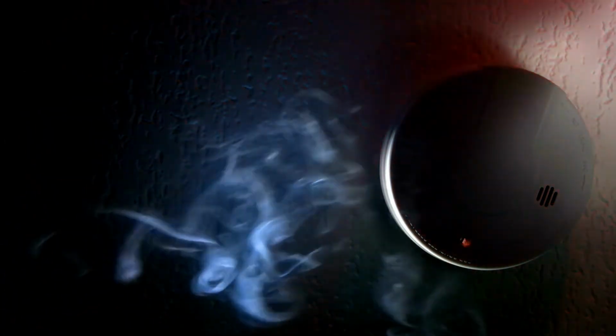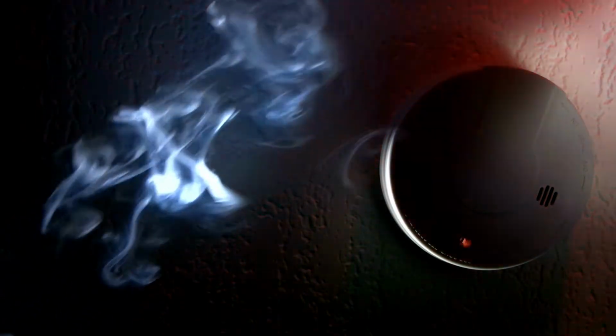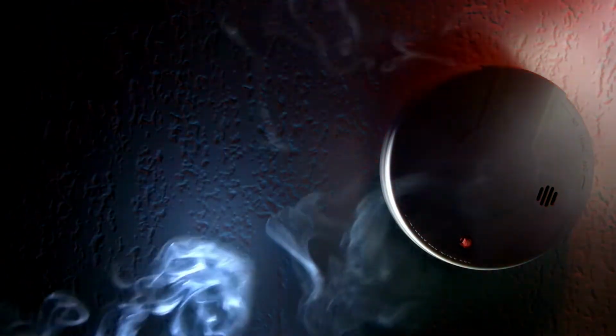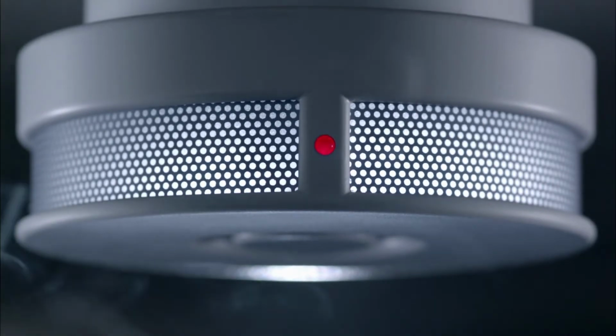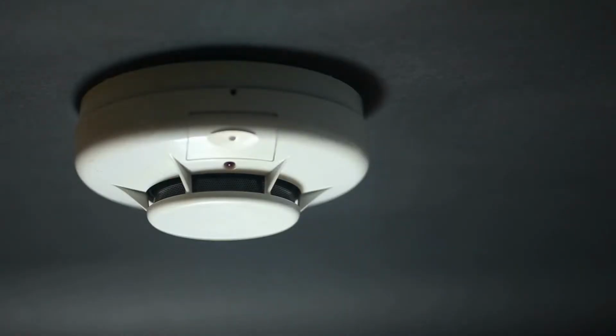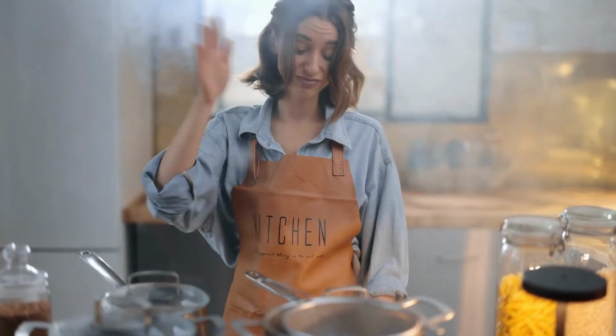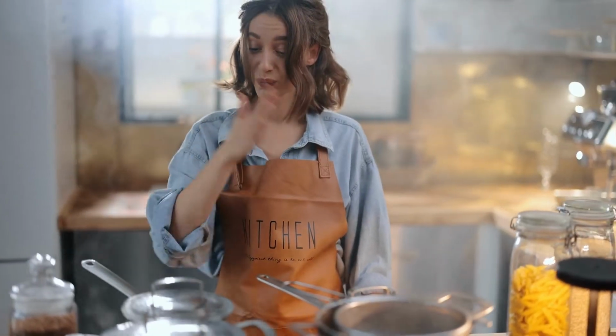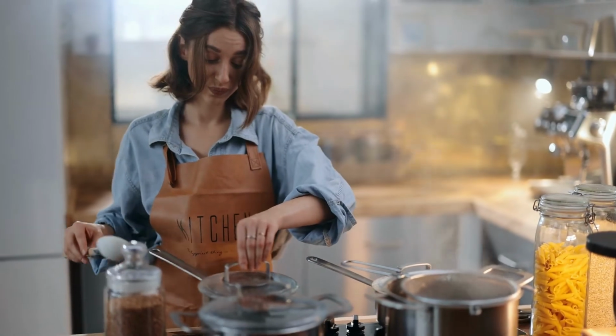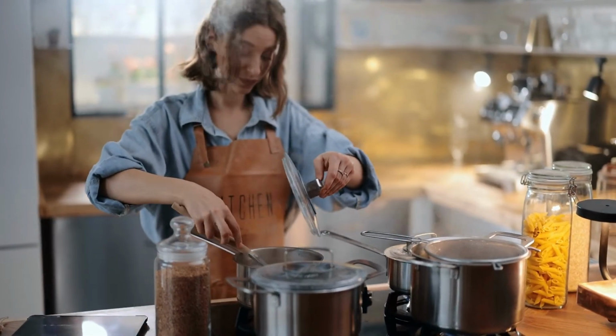Smoke detectors. Smouldering or slow-burning fires can sometimes generate little heat, making it difficult to detect via heat detectors. Smoke detectors are activated when they detect smoke and may release an audible alert earlier in the development of a fire. In some cases, smoke detectors are recommended over heat detectors, since they can detect a fire before heat detectors can. However, if the alarm's coverage space accumulates dust, this can elicit false alarms. Therefore, heat detectors might be a better fit for some people. Smoke detectors can also be triggered by burnt food and steam, so they're not always recommended for installation in a kitchen or a room where people smoke. However, the technology for smoke detectors has improved over the years, enhancing the fault detection of cooking alarms.